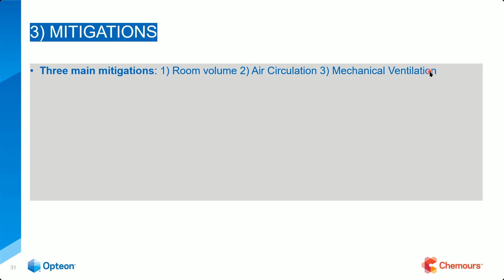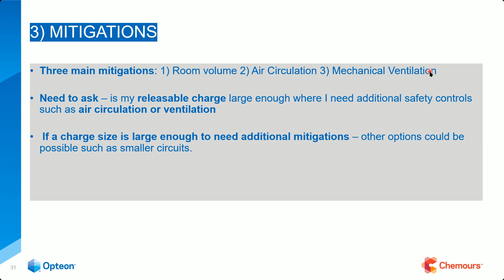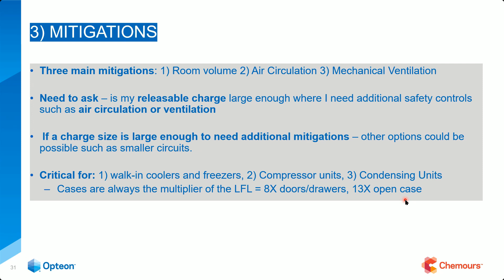So, you need to ask yourself, is my releasable charge large enough that I need additional safety controls such as air circulation and/or ventilation? If a charge size is large enough to need additional mitigations, other options could be possible, such as smaller circuits, so more lines, more evaporators. Critical for walk-in cooler freezers, compressor units, and condensing units. Cases are always, let me repeat that, cases are always the multiplier of the LFL. So 8 times for doors and drawers, 13 times for open cases.